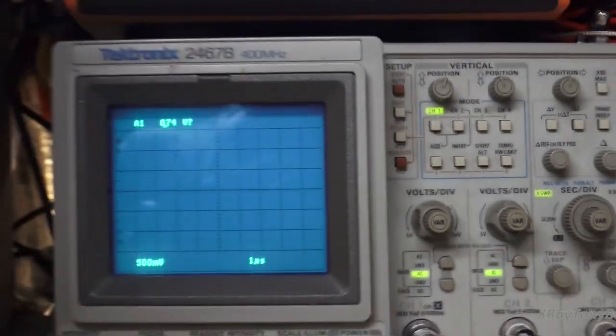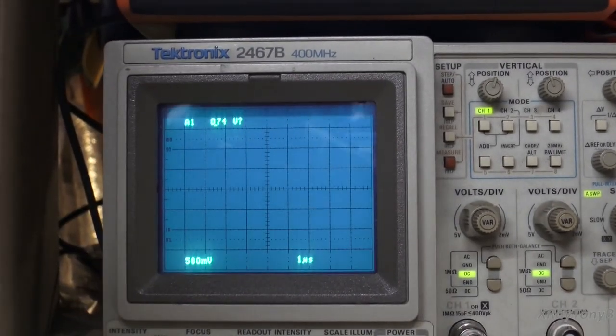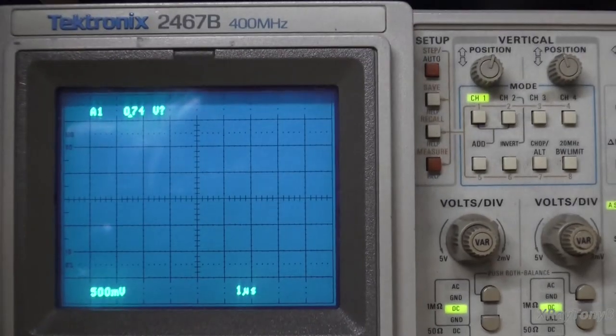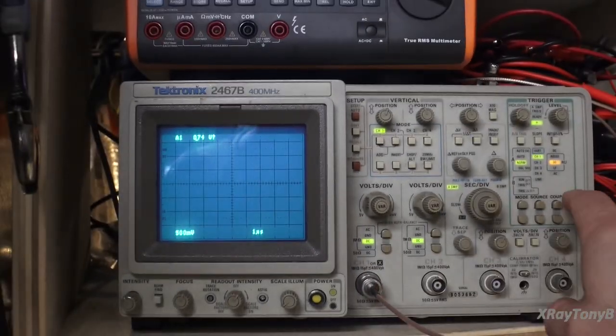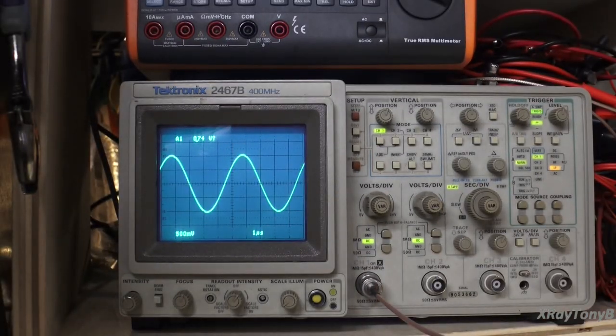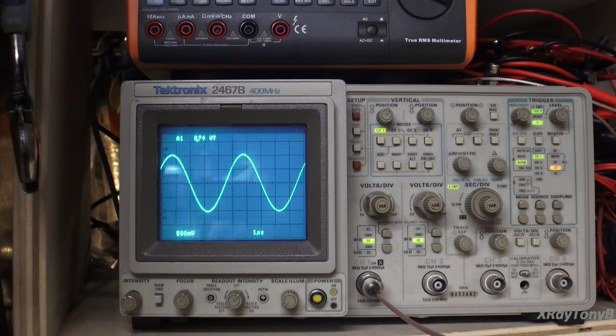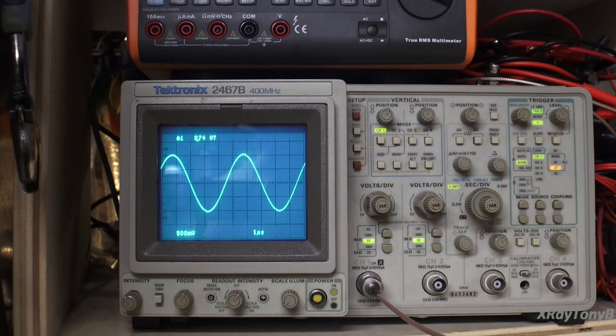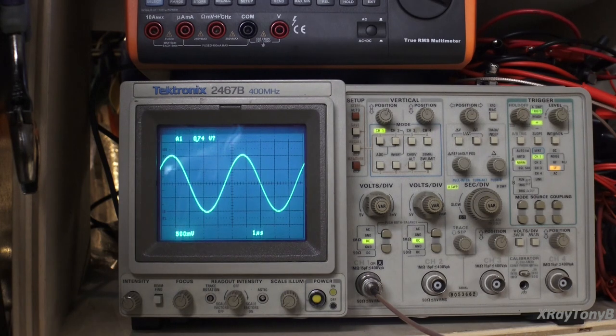If we go back over to our scope, we have no waveform. Now watch what happens when I change it to low frequency reject. Now it comes back. That's a high frequency signal. If you're getting false triggering because you have a complex waveform, for instance, you can use the high frequency, low frequency, and noise reject to reject that component of the waveform that is false triggering and not letting you lock in on what you want.